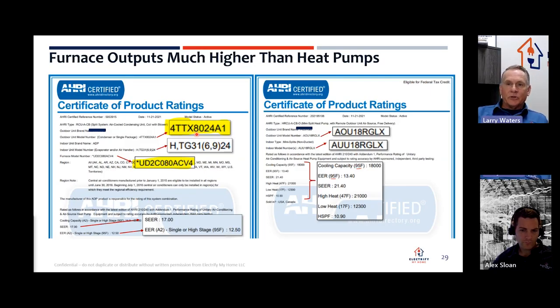So in order for it to be sold as an 18 SEER and just meet this 12.5 EER, the furnace we had to combine this with was massive. So this was an upflow furnace, 2-stage, 80,000 BTU, variable speed 4-ton. So in order to get 12.5 EER, and when I went and looked at all these, I was trying to find the match that had the highest rating with this particular outdoor unit in this size.